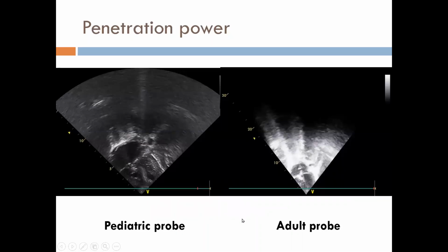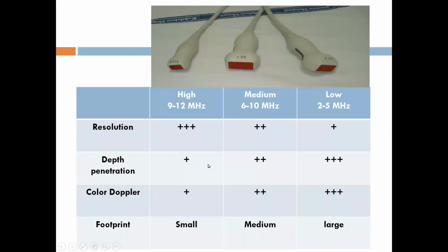This is one of the examples. What we can see here is a high frequency probe and here is a low frequency probe. What we can see here from this is a sector, and the penetration power is up to 30 centimeters. But in case of the pediatric probe, the penetration power is up to 15 centimeters. So the high frequency probe will have a less penetration power and the low frequency probe will have a higher penetration power. So here we are having a differentiating feature.